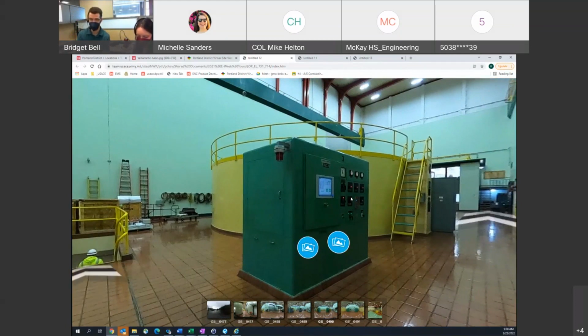Essentially, the governor is a system of pressurized hydraulic oil and valves that pushes oil to our wicket gate system. The wicket gates open and close to allow more or less water to flow through the unit. Before the generator is synchronized to the grid, you use the governor to control the speed of the unit - the more water you have, the faster it spins. Once you synchronize the unit to the grid, it can't change speed anymore because you've synchronized; it has to run at a specific speed. So what you're really controlling is the power output coming through the generator into the transmission lines.